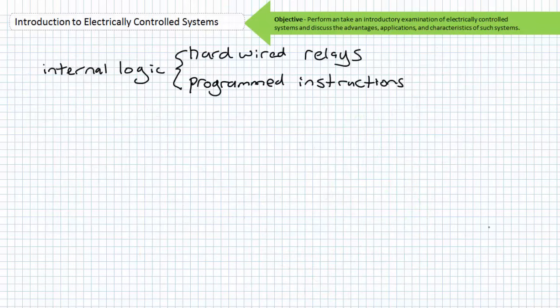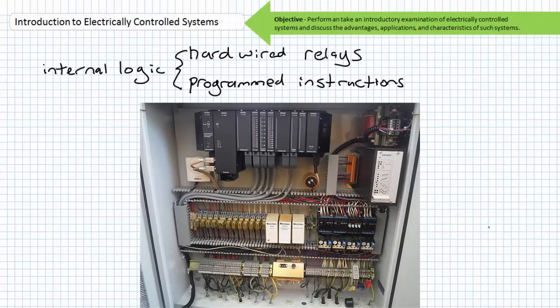Electrically controlled systems can be divided into two general categories: those that employ traditional hardwired relay-based ladder logic and those that use a programmable logic controller, or PLC, a form of ruggedized industrial computer to execute the logical functions necessary to stop, start, change direction, modify operating characteristics, or perform timing, counting, sequencing, comparison, arithmetic, data processing, communication functions, and more. Hybrids of these systems exist.